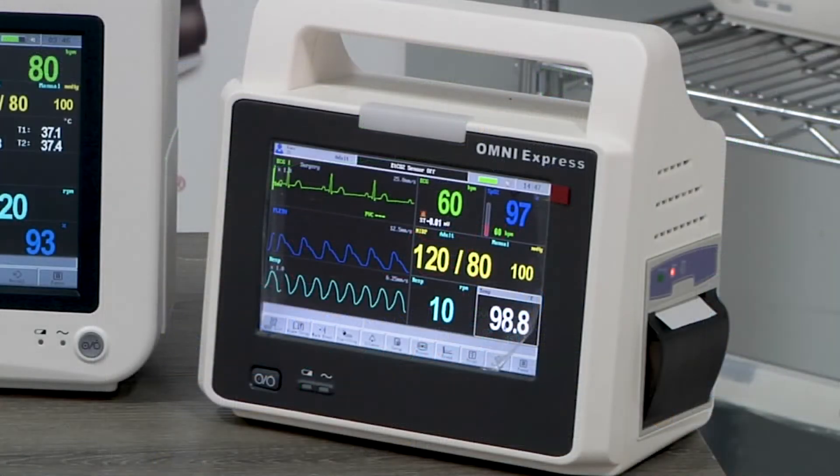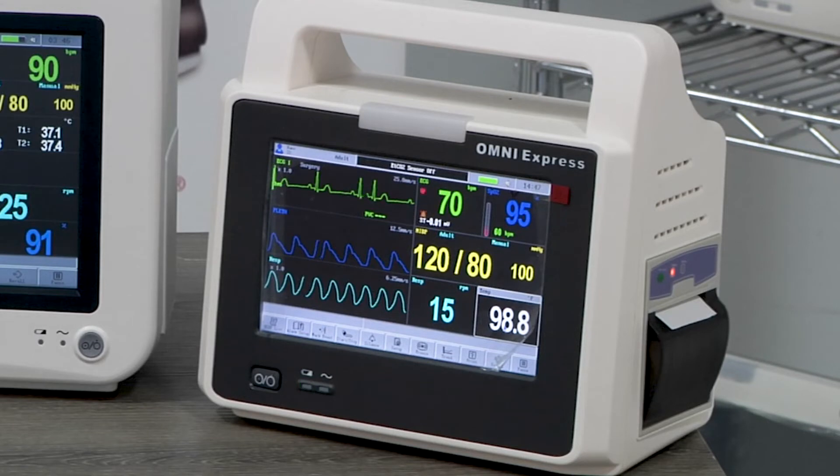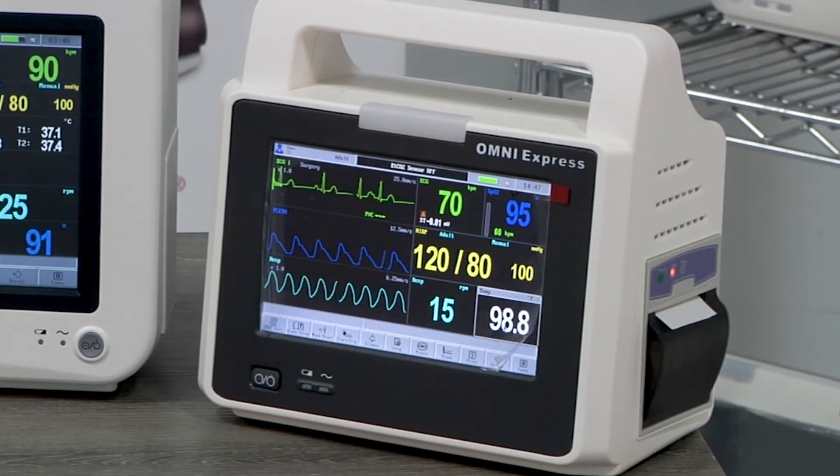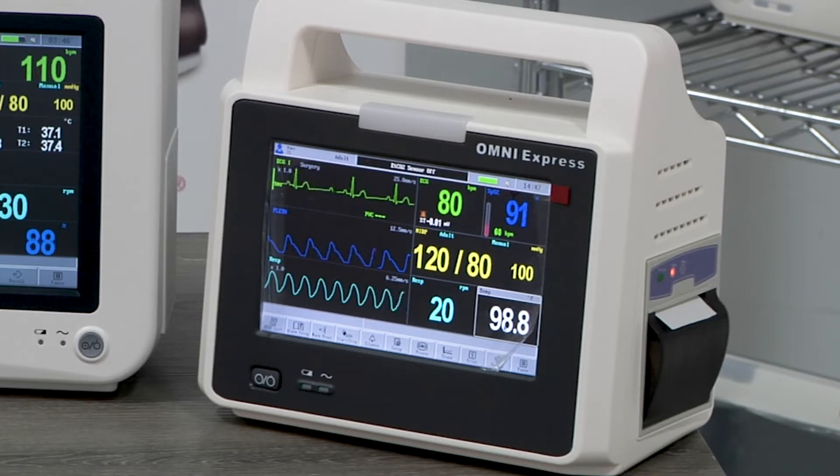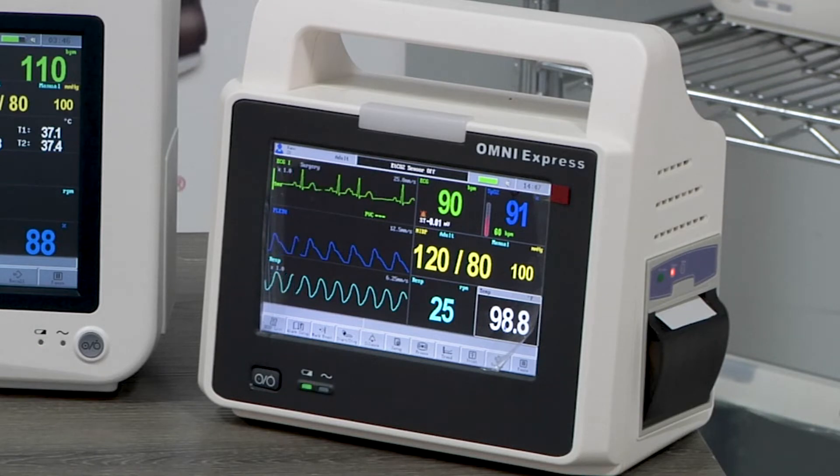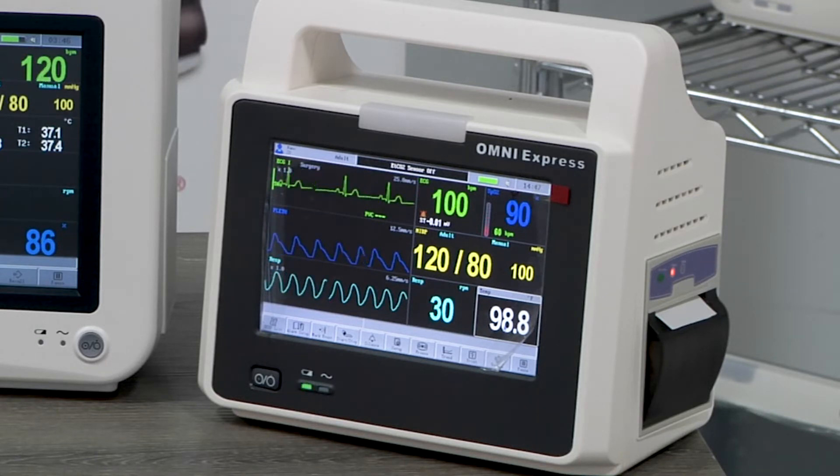Our 7-inch Omni Express monitor has basic functions of 3-lead or 5-lead ECG, respiration, NIBP, SpO2, and 1 channel of temperature. Optional functions include ETCO2, HL7, and external anesthetic gas monitoring.